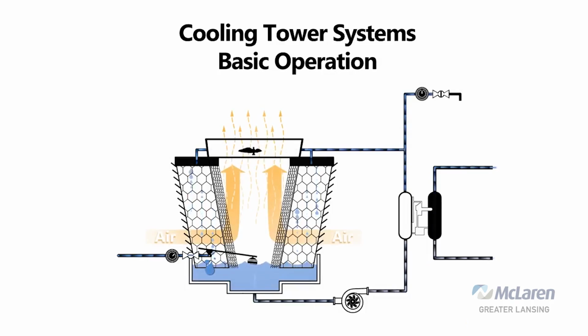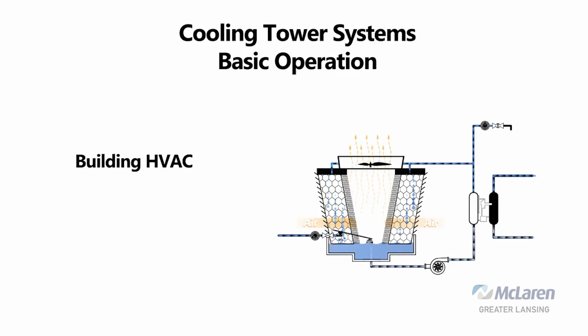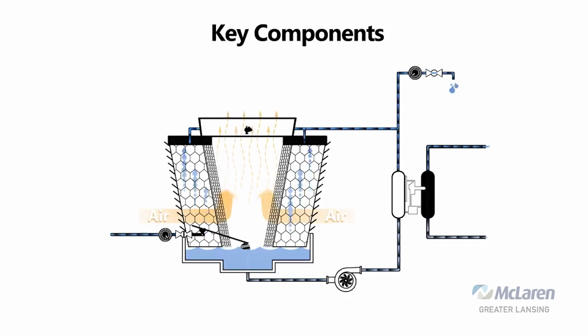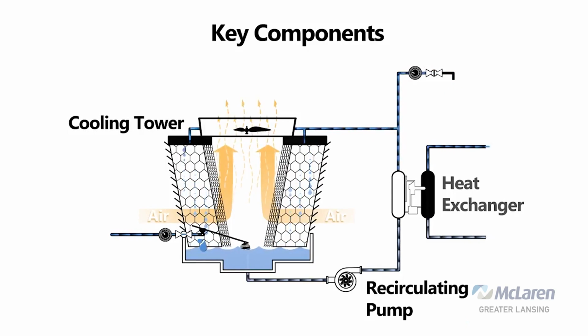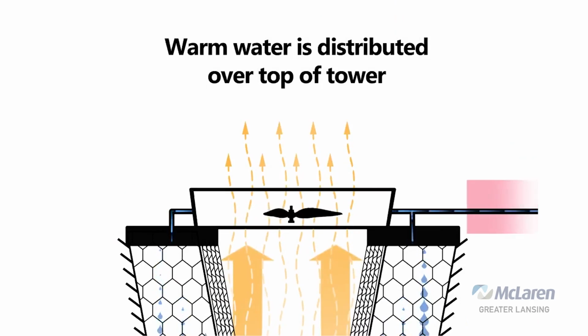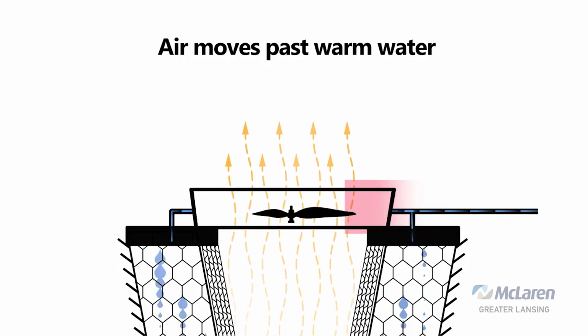However, as condenser water systems get older, the carbon steel pipe develops pipe scale, right? On top of the cooling tower is what we call the hot water basin. There's two on each tower, each cell. The warm water comes in, essentially dumps into the hot water basin, and then by gravity flows over these distribution nozzles, right? And the nozzles will end up plugged. The solution to that is, on top of the fan deck, after you lock out the tower, pull the hot water basin covers off, and reach in and pull the scale out of the nozzles.